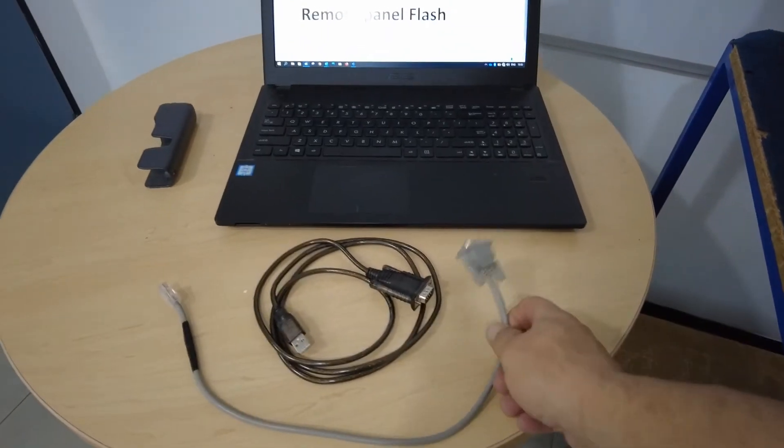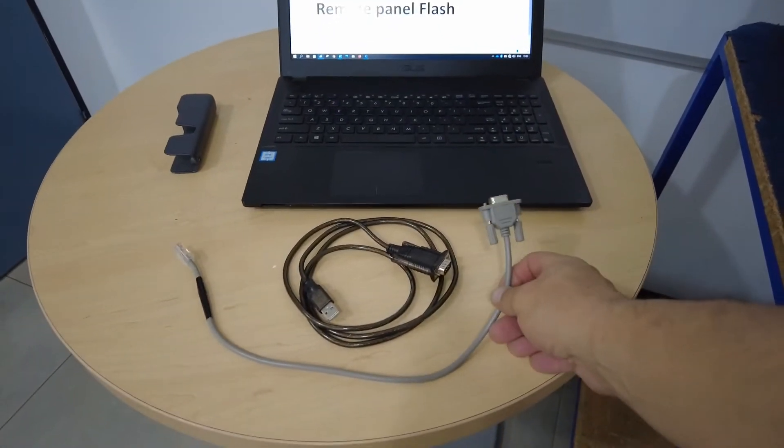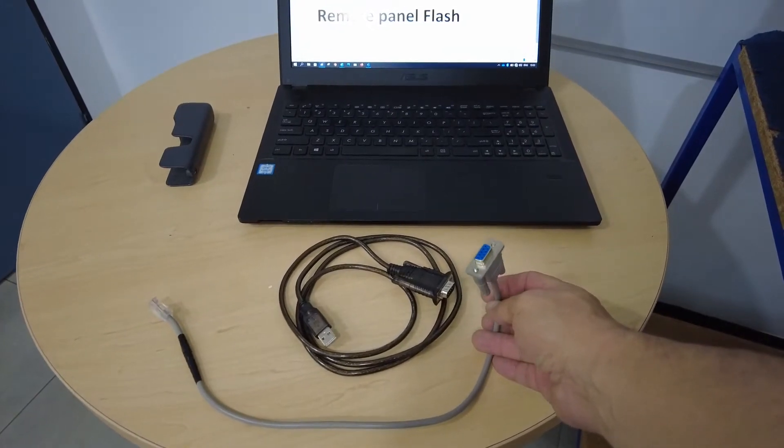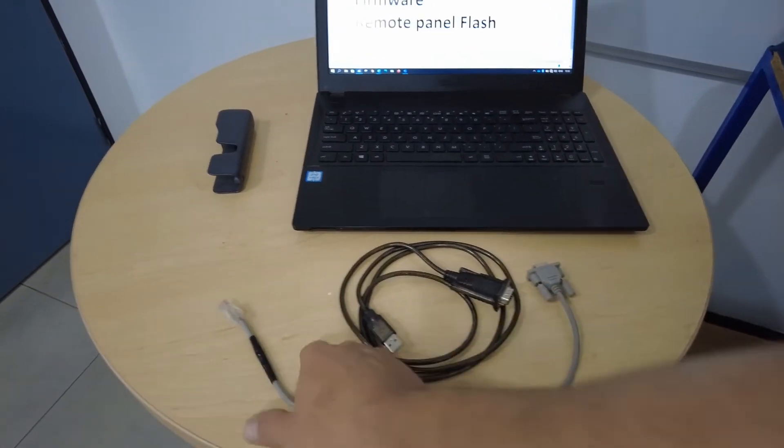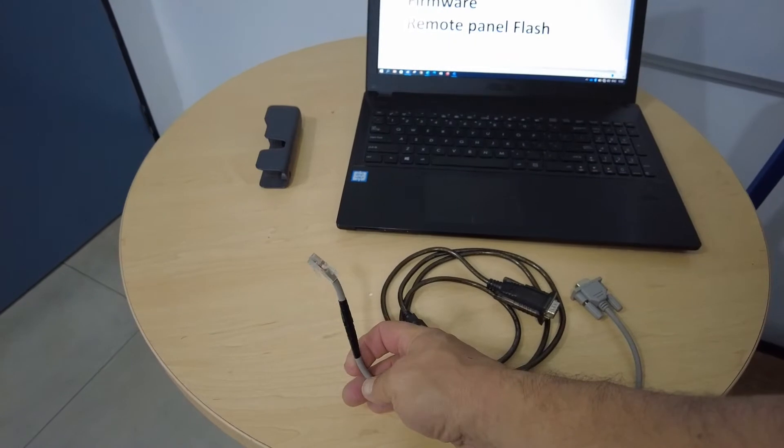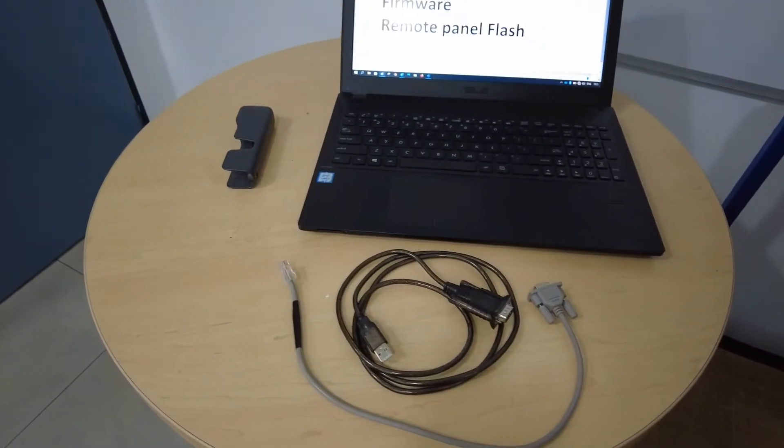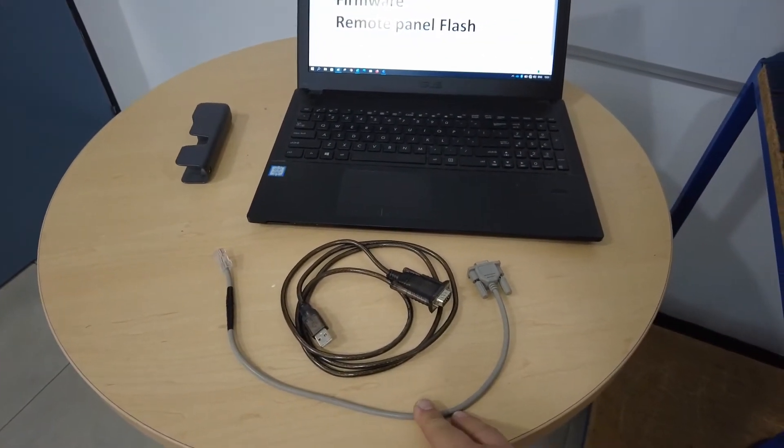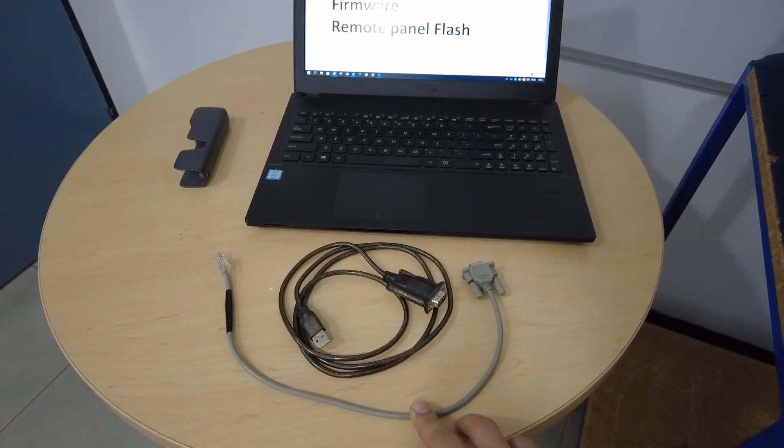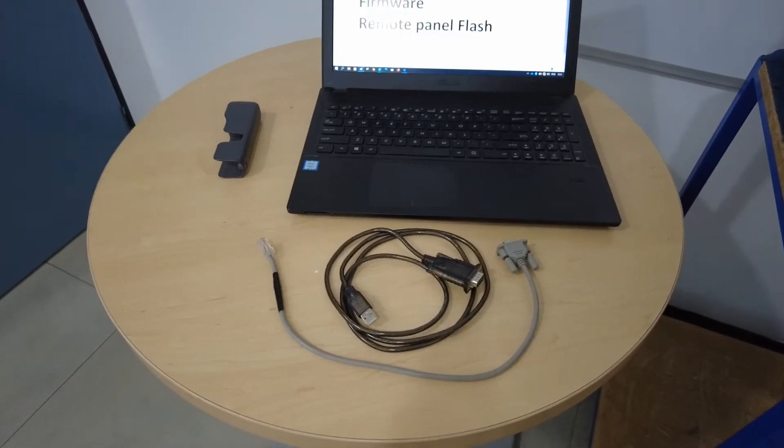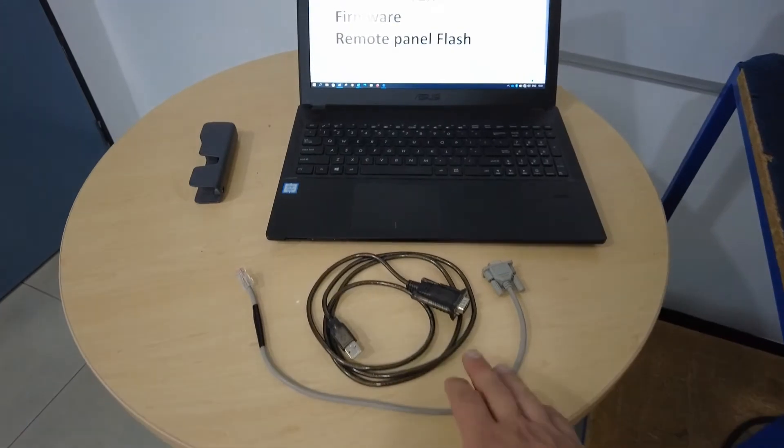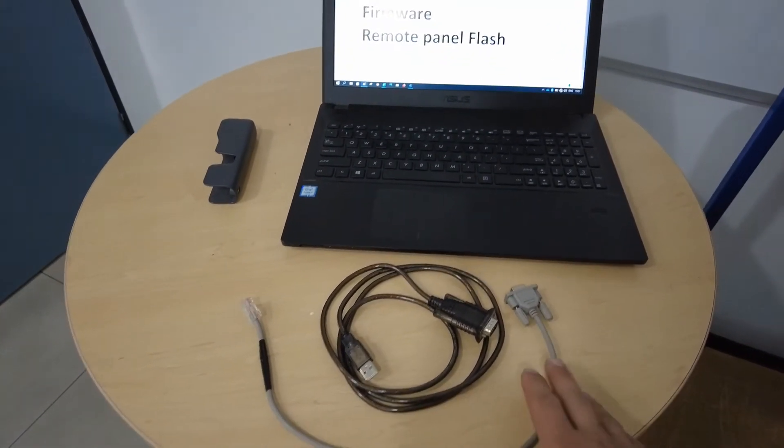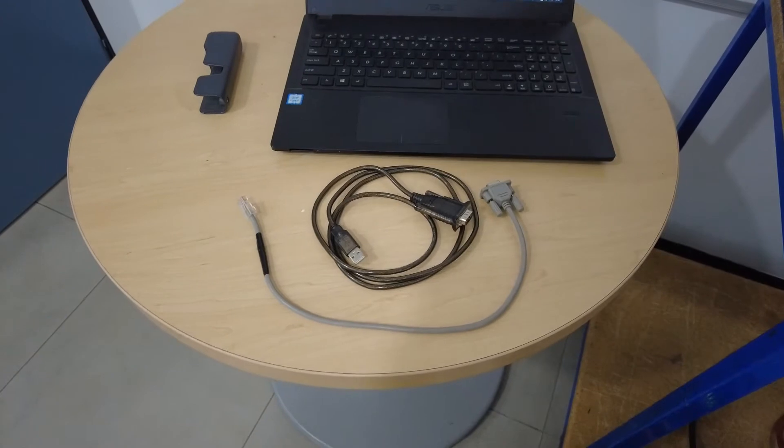Have a look out in the box of the inverter for a cable looking like this. Note you have the serial port on one end and the network RJ45 port on the other. You need to use the cable that came with the inverter in the box. Do not buy cable online because the pin outs for that cable is different. Please do use the one that's provided with the inverter.